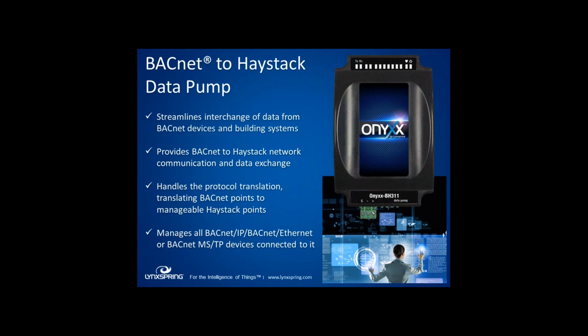Okay, so designed to streamline and interchange data from BACnet devices and building systems, the Onyxx BACnet to Haystack Data Pump provides BACnet to Haystack network communication and data exchange to Haystack servers. It handles the protocol translation for BACnet points into representative Haystack points, BACnet devices and associated equips to Haystack devices and associated equips. It manages the BACnet network, IP or MSTP.